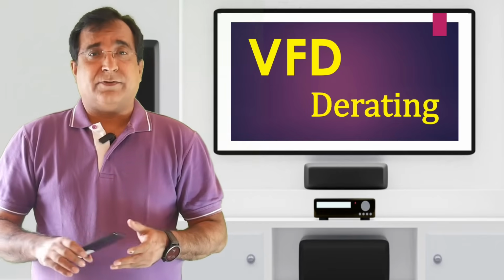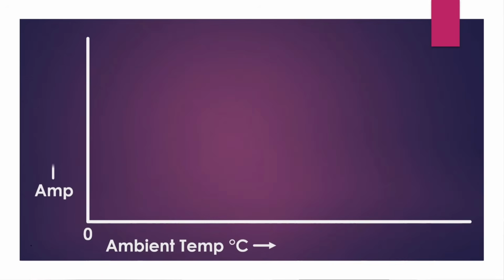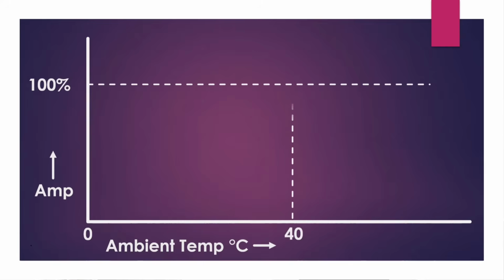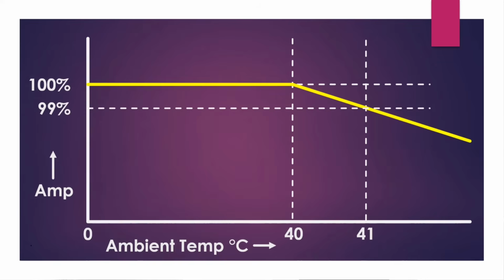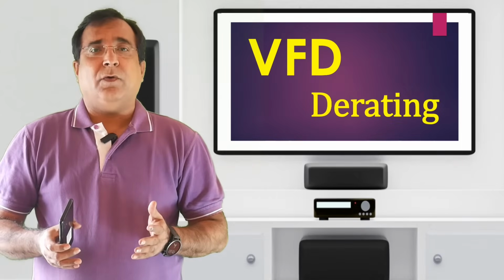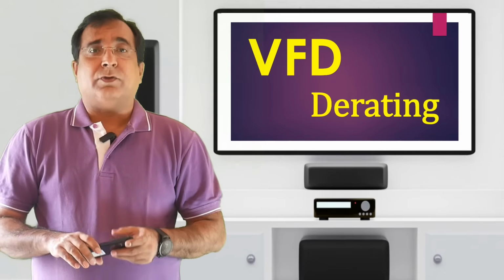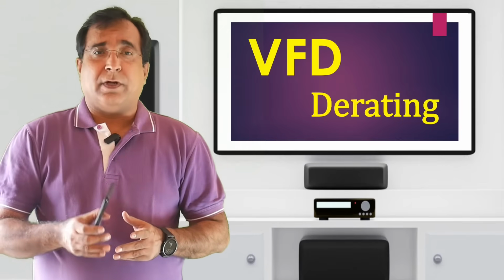Okay, let's consider the situation. The VFD is installed below 3300 feet. But if the ambient temperature surrounding the VFD goes up, the VFD also derates by 1% per degree Celsius, as discussed earlier. That's why VFDs are always installed in an air-conditioned panel room to keep the temperature below 40 degrees Celsius, so that we can encash its true full capacity.